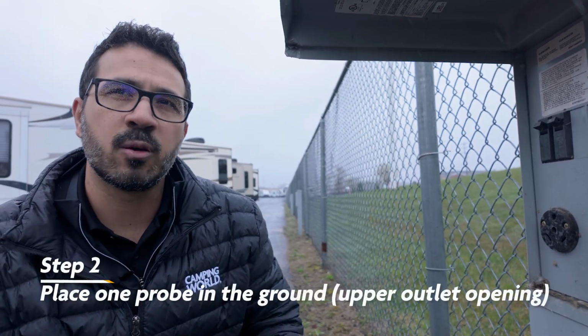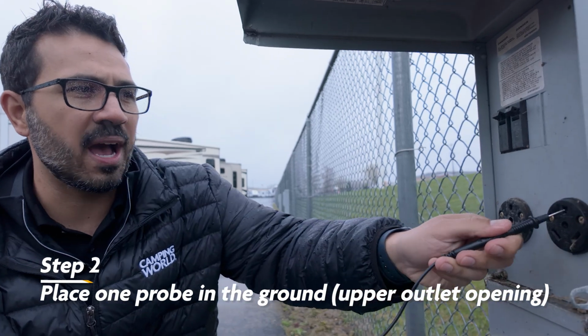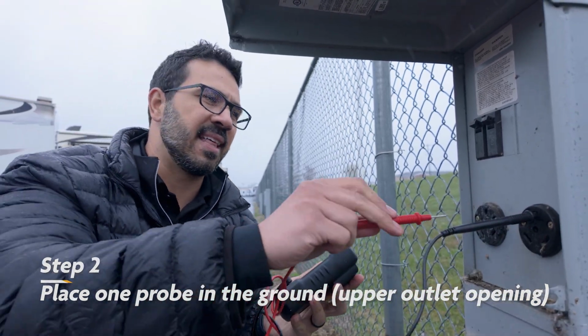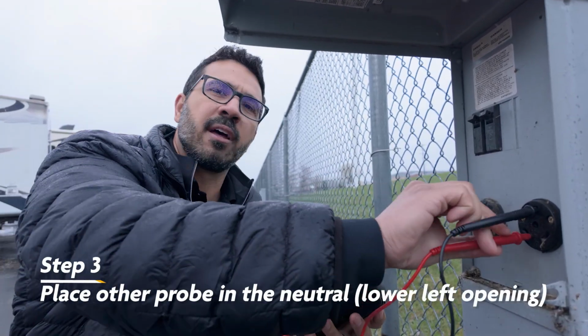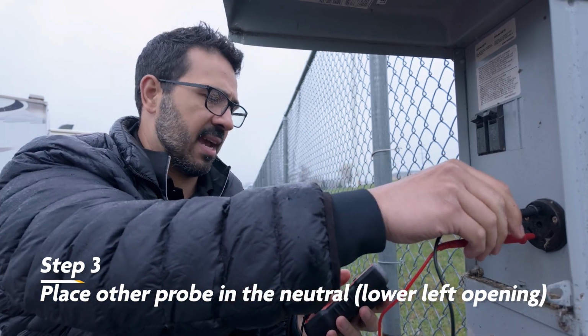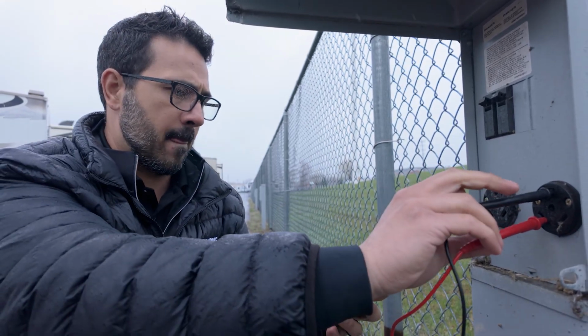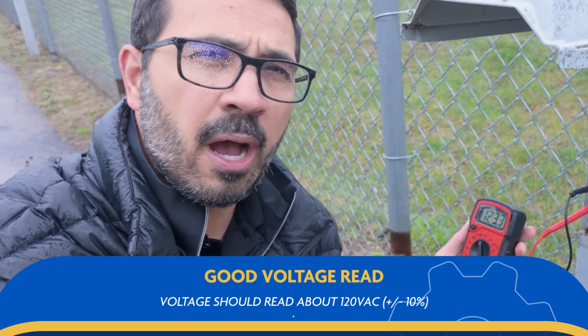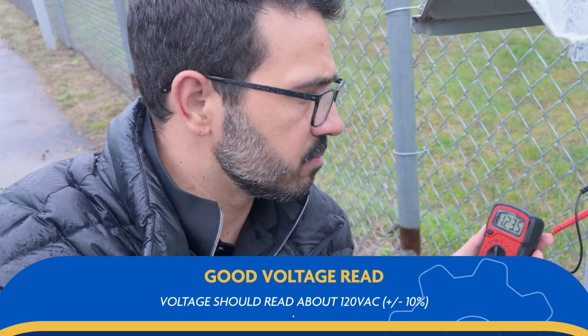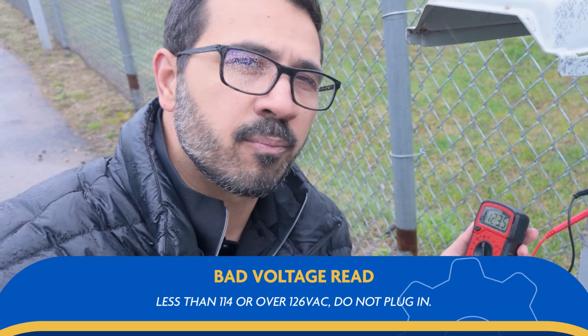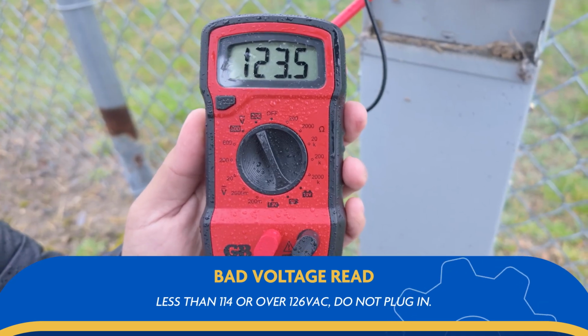To perform the test, you want to put one probe into the ground and the other into the hot. You may have to wiggle it a little bit to get an accurate reading. Now, it should read right around 120 volts AC. If it's less than 114 or over 126, you probably shouldn't plug in due to a risk of damaging your appliances. Now, what if you're plugging into 50 amp?